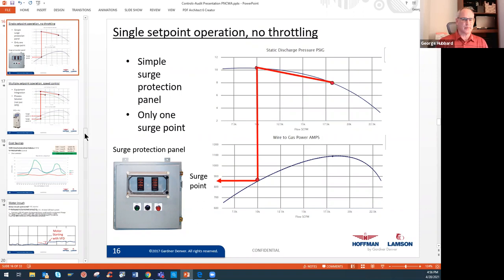I had mentioned during the presentation all the variables: you could have ambient temperature, you could have DO, you could have header pressure. You can combine all of these inputs and then have the controller take a look at where it's operating on the curve and make adjustments as required. So we can accommodate for header pressure. But usually we're not in control of it. It's usually the downstream piping and the basin head level that will dictate whatever pressure it's running at.